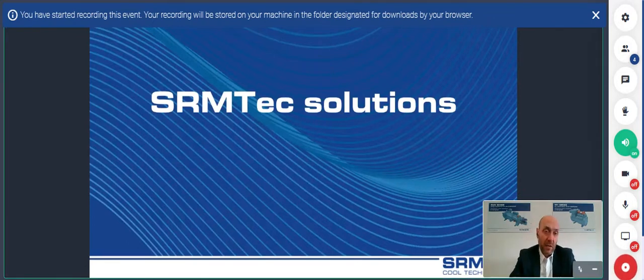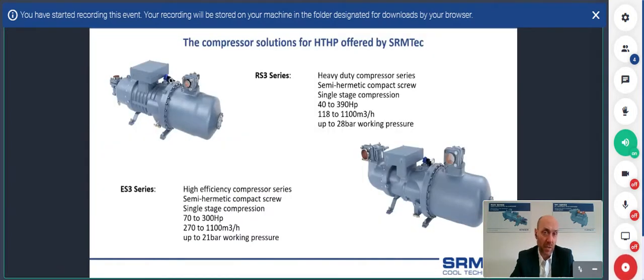So, which are the solutions that SRMTec can offer? We have mainly, we are considering this range, semi-hermetic screw compressors. These are a compact type, so with integrated oil separator. And we have two different series. The other series is a heavy-duty compressor series with a nominal power between 40 and 390 horsepower, with a working pressure up to 28 bar. The second series that we can promote is the ES3 series, suitable for lower pressure ranges, still with a larger range of displacement, and they can express a little higher efficiency in the application range.